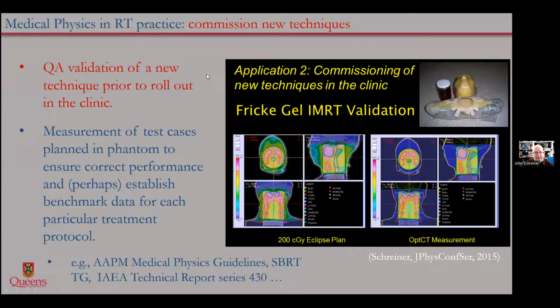And just to give a few more examples of what physicists would do, if we have a new technique that we want to use, the physicists will usually do a lot of testing before that technique is delivered on a patient to ensure that the technique can be delivered. So here's an example of some measurements we did with a particular type of dosimeter that could measure dose in 3 dimensions. Before we did our very first intensity modulated treatment in our clinic, we actually simulated that treatment on a test phantom, a thing that simulated a head and neck. And we put in this detector and we assured ourselves that the doses we were delivering were the doses that the treatment planning system and our process was predicting.